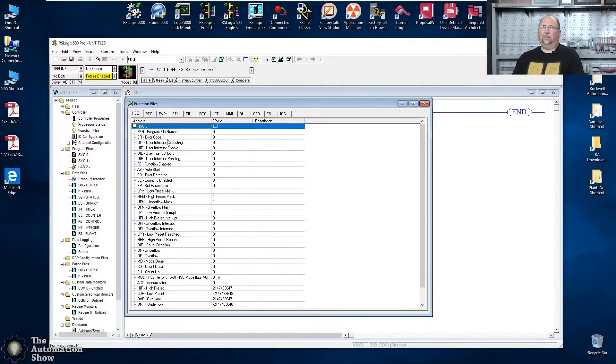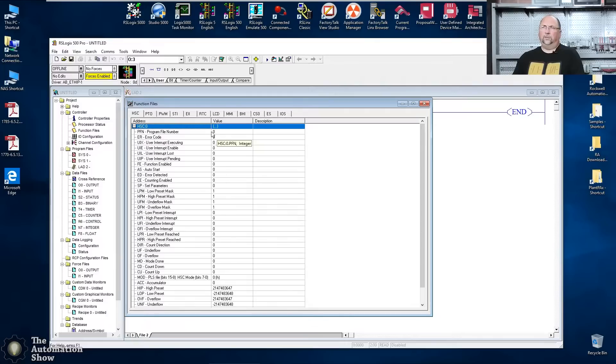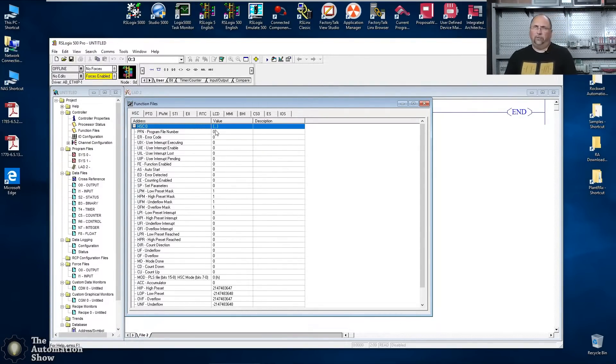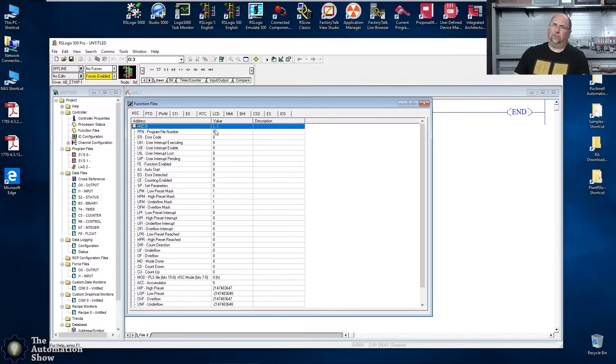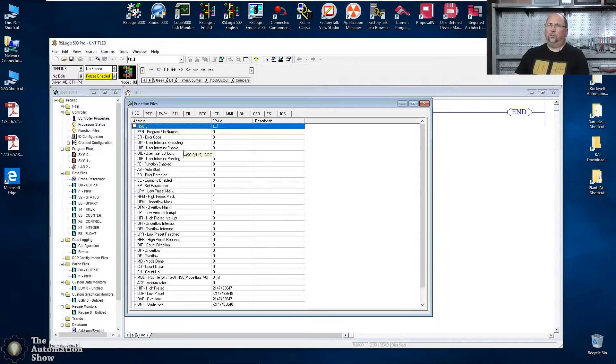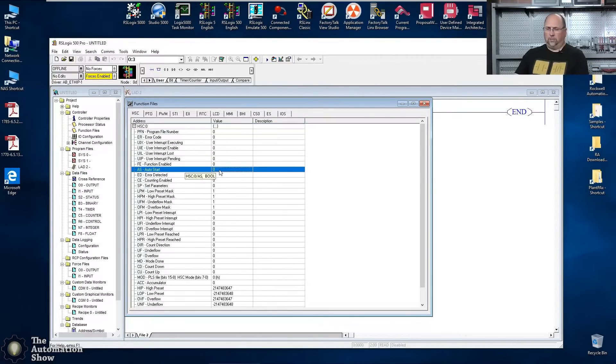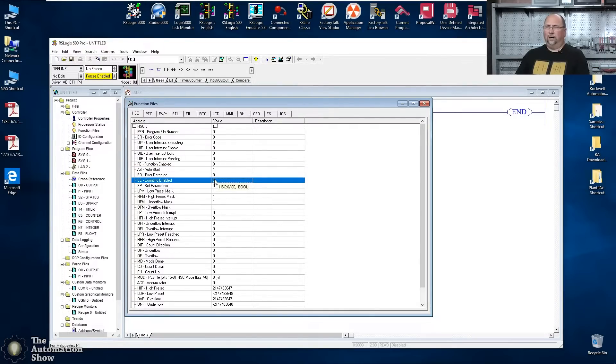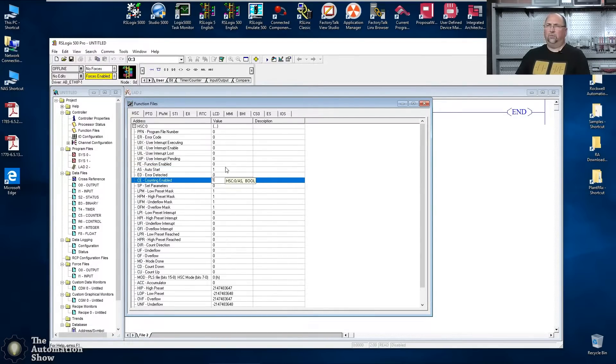And now we'll go into the function files for the counter here and we have HSC zero. And if we look here, we can see, first of all, program number. Now I don't want to give it a program number. I'm not going to use the interrupt, but if I don't, it faults the controller and I'll show you that. We'll leave that blank right now.